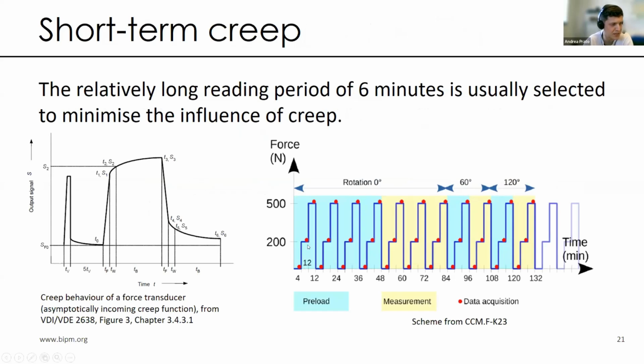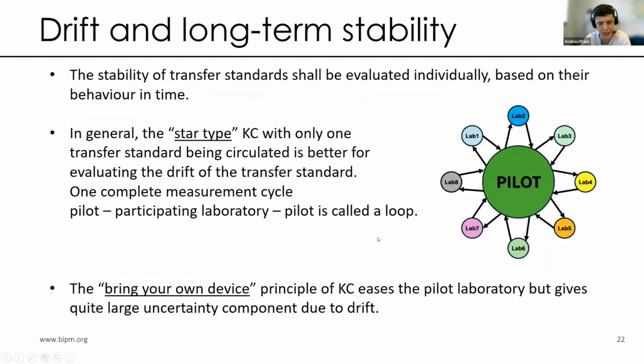We can see here an example of a scheme of a key comparison procedure. We keep on applying different force or torque steps, and we acquire data after 6 minutes from the application of the force or torque signal. In this way, we are quite sure that the short-term creep can be minimized, since the deformation becomes very small at longer time periods. The other important influence factor is the drift and the long-term stability of the transfer standard, and this shall be individually evaluated for each transfer standard in order to evaluate its behavior in time.